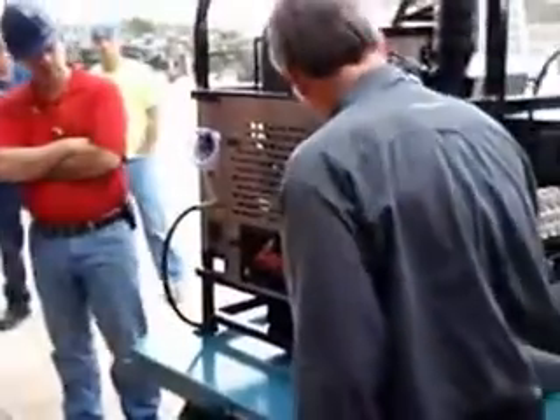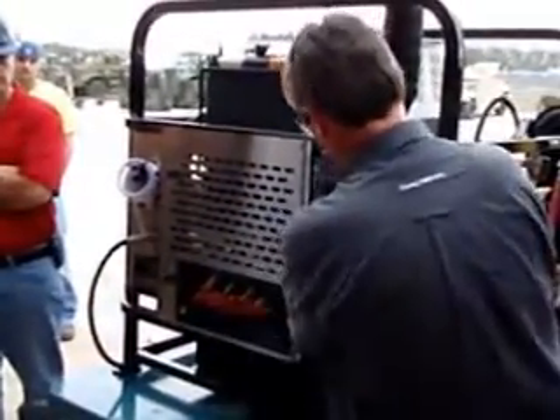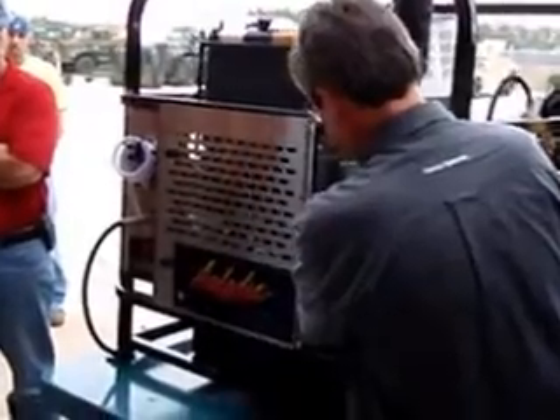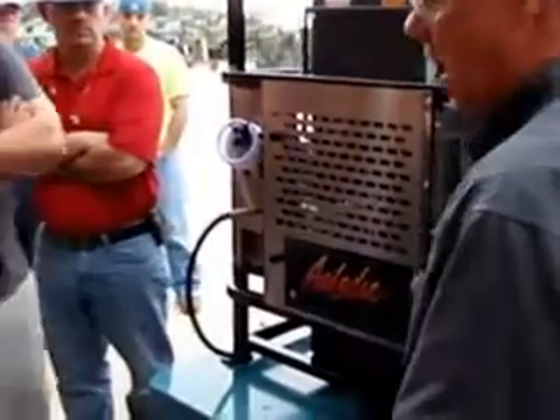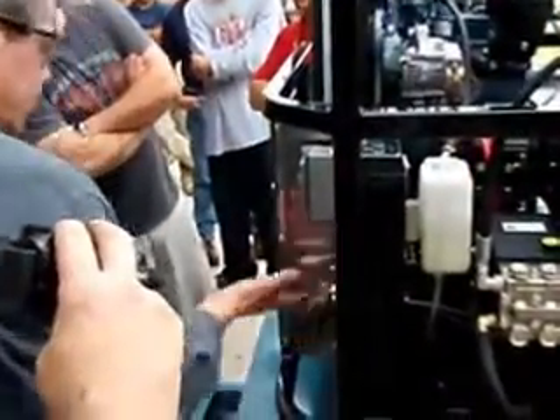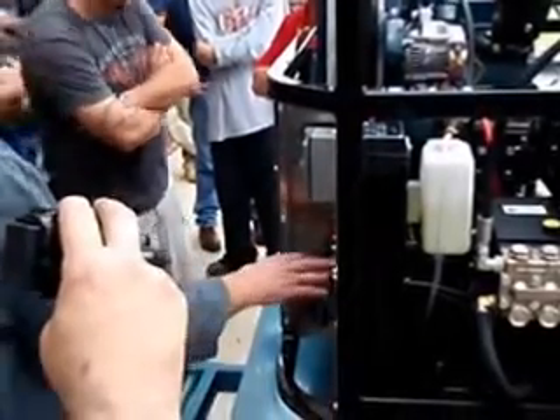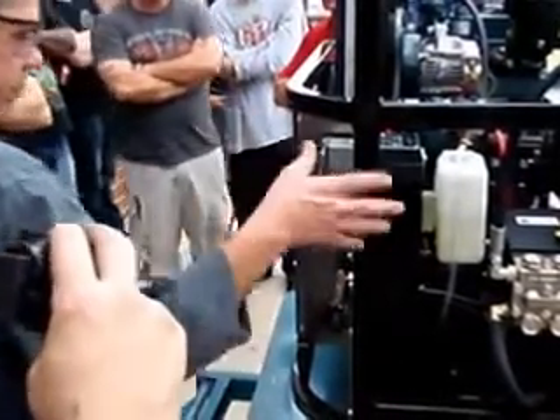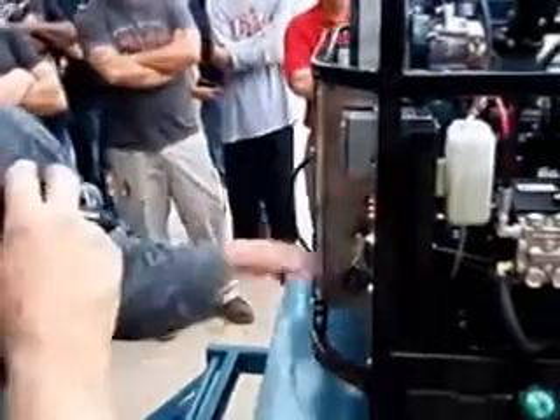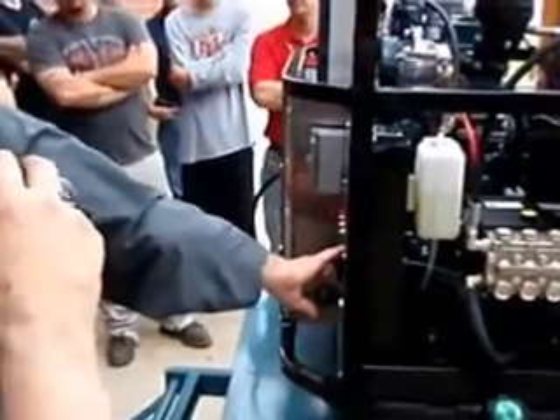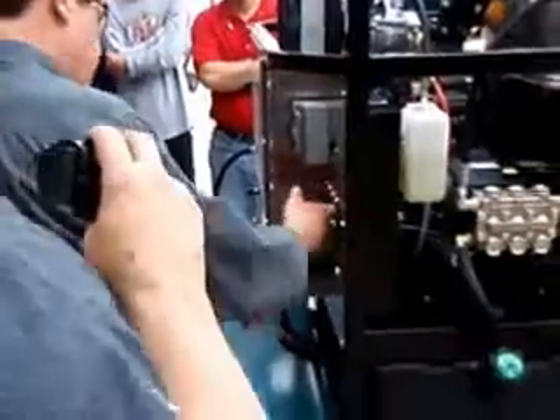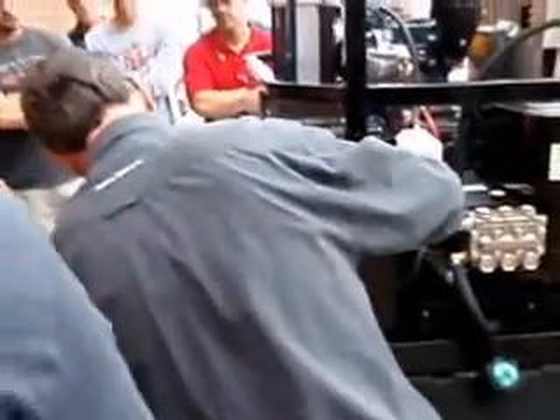You've got your key switch. You're going to turn your key switch and let your glow plug lamp heat up and go out. Once it goes out, you're ready to fire. So you just turn it to the left, preheat, the glow plug goes out, then you're ready to fire. Turn the machine on, let it build up pressure. Once you've got full pressure, then you're ready to engage your burner system. You've got a thermostat here. It can be adjusted to whatever temperature you're looking to achieve.